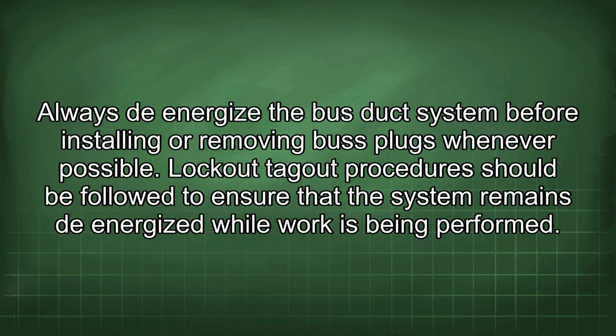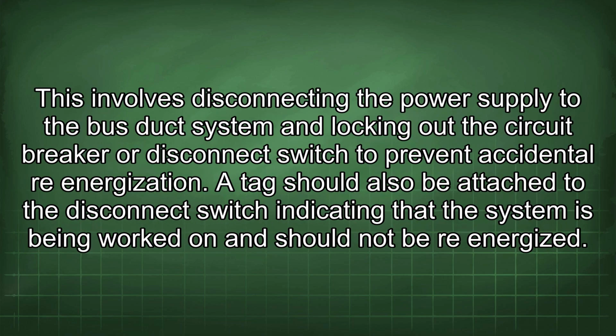Always de-energize the bus duct system before installing or removing bus plugs whenever possible. Lockout-tagout procedures should be followed to ensure that the system remains de-energized while work is being performed. This involves disconnecting the power supply to the bus duct system and locking out the circuit breaker or disconnect switch to prevent accidental re-energization. A tag should also be attached to the disconnect switch indicating that the system is being worked on and should not be re-energized.